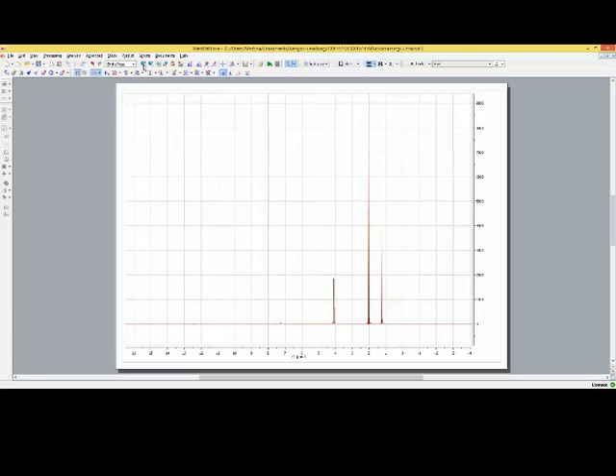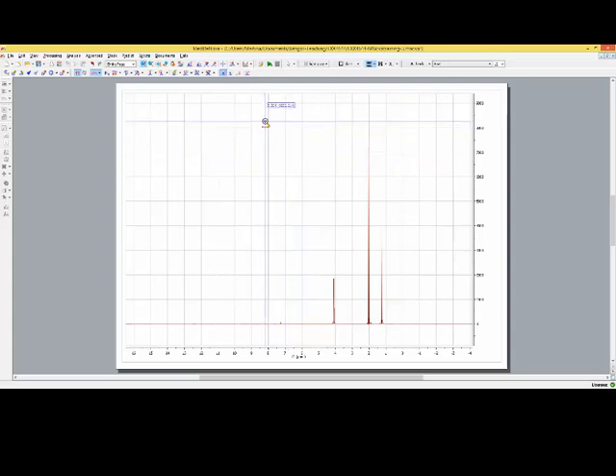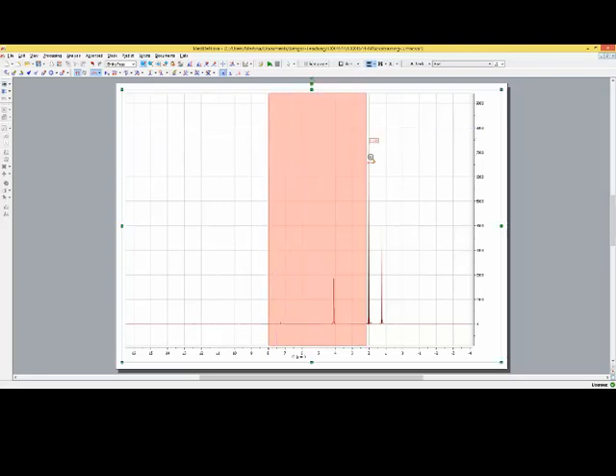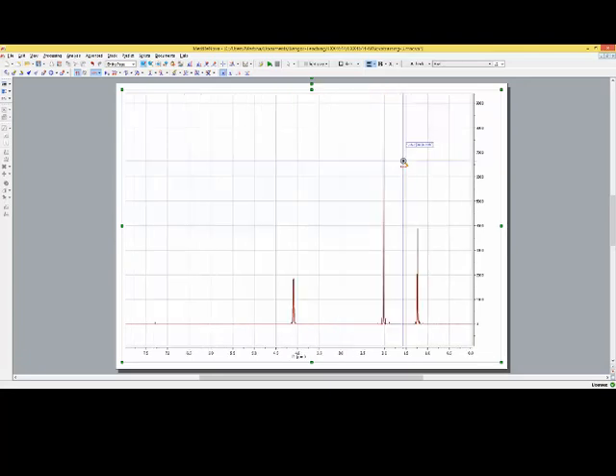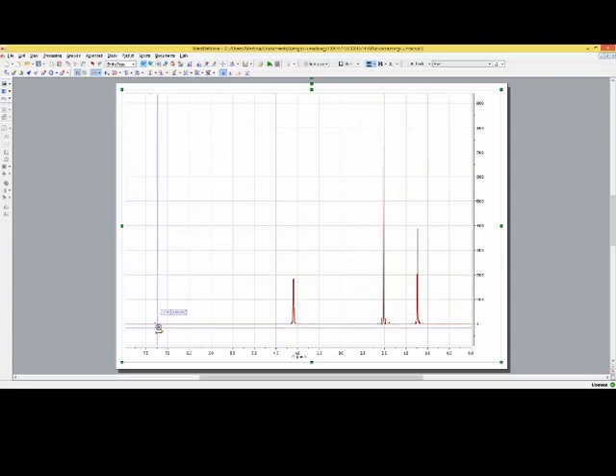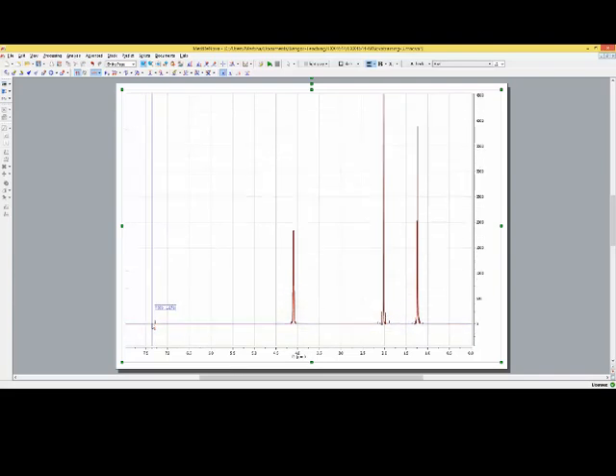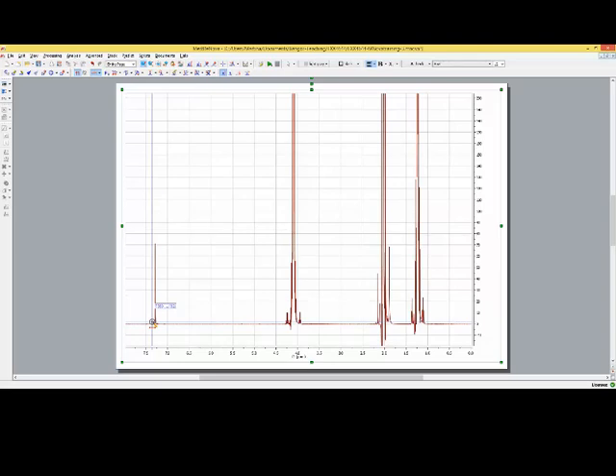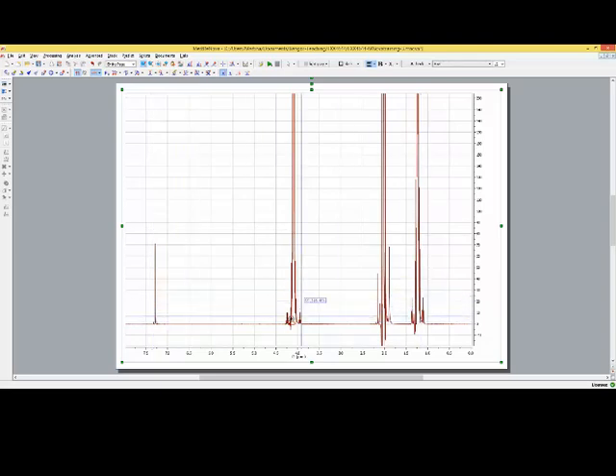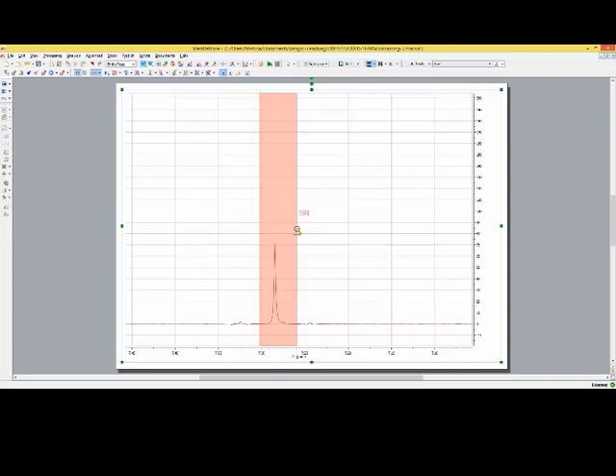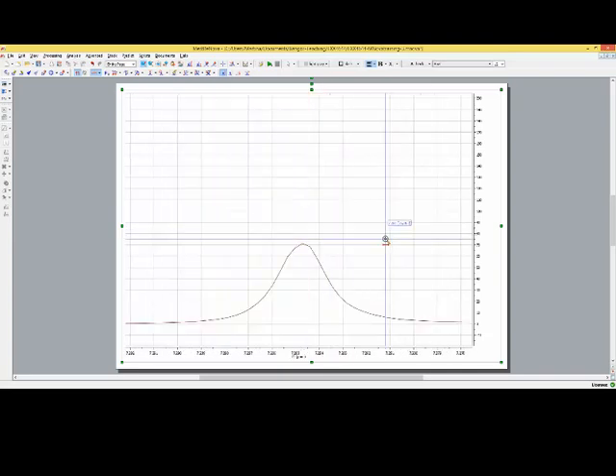So for this purpose we need a slightly bigger peak. Let us zoom. Here we have on the top menu we have a zoom tool. If we click this one we have now activated. You can see this activation by seeing that the icon gets a bit darker. So now I move my mouse pointer so that I include all the peaks both in terms of heights and widths. And then I hold my left mouse button down and just drag it. So in this case I decide to go from 8 to 0. I would like to set the reference peak. For this purpose I need to get this reference peak, my chloroform peak, a little bit bigger. So I'm first wheeling up my intensity. Don't worry about the funny shape of the other signals. And now I'm starting to zoom in this peak until I get a nice big peak in my spectrum.